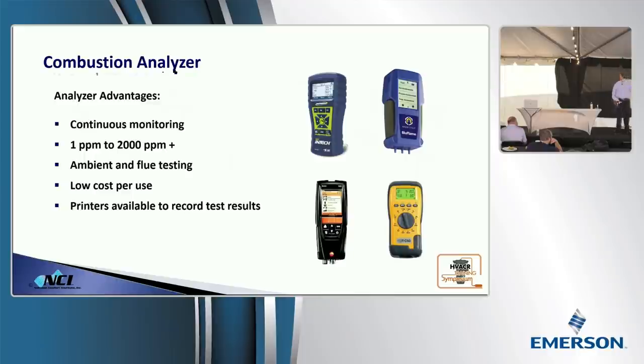Now, is it a good idea to use your analyzer for your personal protection device? Everybody do this. Because once you take the analyzer probe and you insert it into the flue, which is the proper place to test, now you have no way of monitoring the ambient space. You need two separate devices, one for personal protection, which has both an audible and visual alarm on it, and then you need something to actually measure the flue gases with.